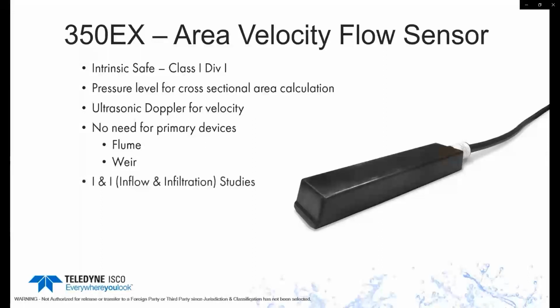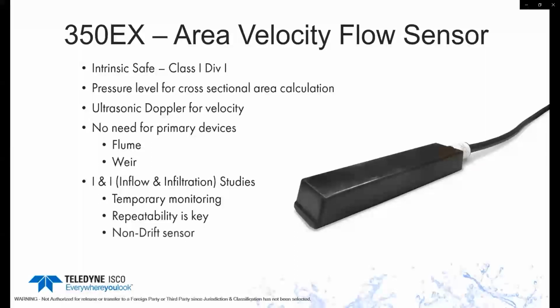Most commonly, you'll see these used with I&I, again, inflow and infiltration studies, or as my buddies in Europe would call them, flow surveys. Temporary monitoring, very popular for that, because all you have to do is put it on a ring, put it in the pipe, set the level, and away you go, and you're pretty well done. What they're most concerned with in something like that would be repeatability. So it's not typically for billing when you're doing I&I. This is looking at maybe capacity, or what happens in this part of town when I have an inch of rain in that area. But they want to be repeatable. They want to know again the magnitude of what's happening in there. So what's key is having a non-drift sensor. So whatever design you look at, you want to make sure that thing is as stable as possible.